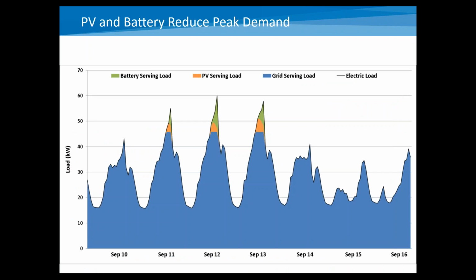So this is what the system looks like during a typical operating season. We're just showing 1 week in September, but you'll see that the PV and battery are working together to reduce that peak load. And this is where the primary source of savings is coming from for these systems. So whereas the peak would have been 60 kilowatts before on September 12th, now it's around 45 kilowatts. So you're seeing a 15 kilowatt reduction in peak demand. And that's providing a lot of the savings that this site gets from installing the PV and battery system.